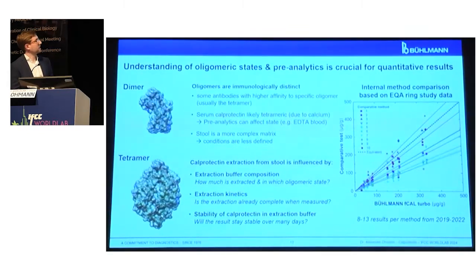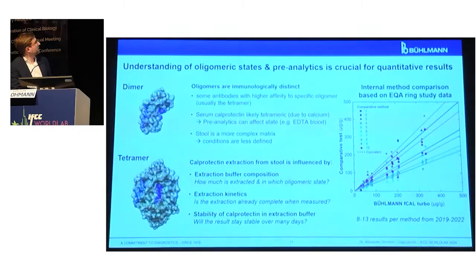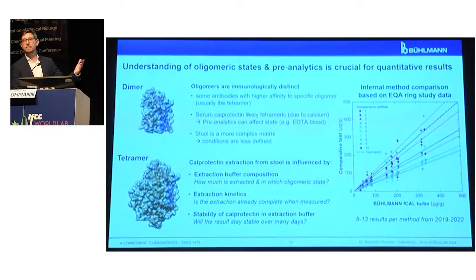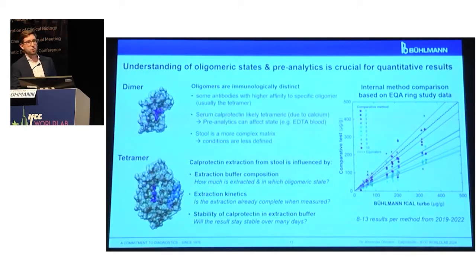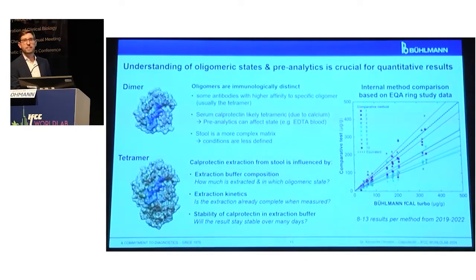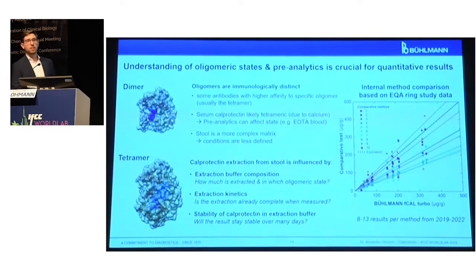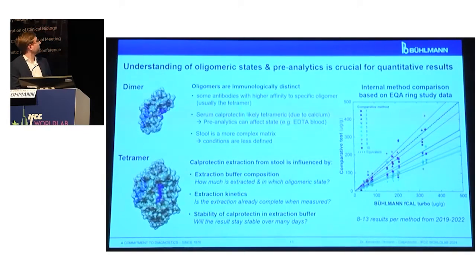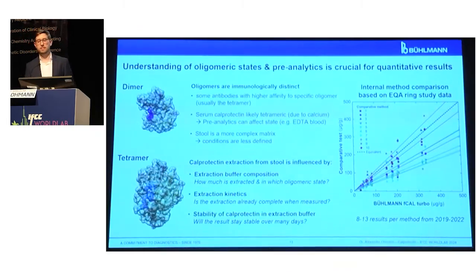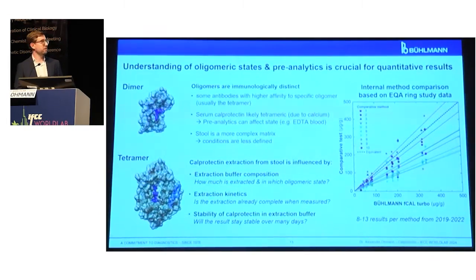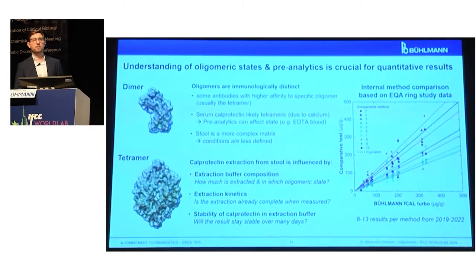We conducted a method comparison based on an external quality assessment ring study, comparing ten different tests on the market — including ELISA, chemiluminescence, and turbidimetric assays — against our turbidimetric Bühlmann F-Cal Turbo. The quantitative results vary quite distinctly, by a factor of about three between the lowest and highest results. We believe this comes down to the oligomeric state being recognized differently across different suppliers, as well as differences in pre-analytics and how the stool is treated. At Bühlmann we are very interested in harmonizing these results so they yield the same quantitative values across multiple suppliers.